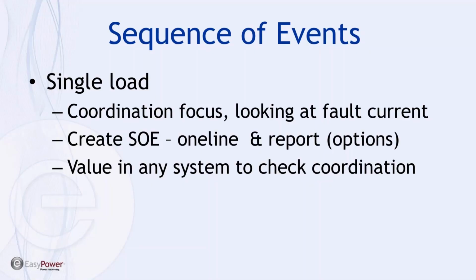And hopefully, as you see me walk through this example, you get a little bit more feel for that. It is possible to create a sequence of events for just one bus or the entire system. And often when I talk about this, it is not a way to do the TCC coordination, but it is a way to estimate how much time you're going to have to spend based upon how many protective devices seem to be out of whack. And especially if you're doing a study on an existing system where presumably it was coordinated at one point in time, sequence of events is a nice way to check system coordination without a whole lot of extra effort. So again, there's multiple places where it can be picked up and used.